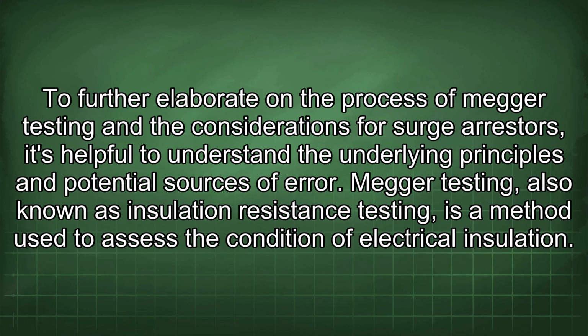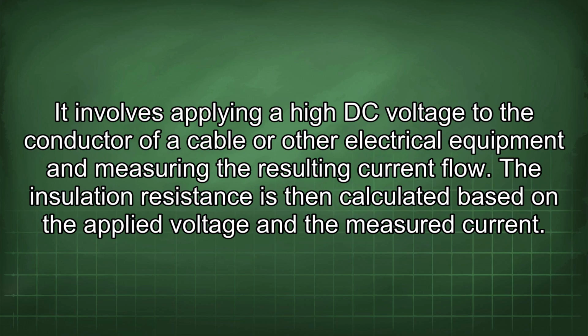To further elaborate on the process of Megger testing and the considerations for surge arrestors, it's helpful to understand the underlying principles and potential sources of error. Megger testing, also known as insulation resistance testing, is a method used to assess the condition of electrical insulation. It involves applying a high DC voltage to the conductor of a cable or other electrical equipment and measuring the resulting current flow.